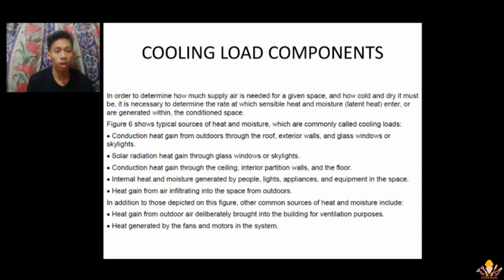Conduction heat gain from outdoors through the roof, exterior walls, and glass windows or skylights. Solar radiation heat gain through glass windows or skylights. Conduction heat gain through the ceiling. We have the internal heat and moisture generated by people. And we also have heat gain from air infiltrating into the space from outdoors. In addition to those depicted in this figure, other common sources of heat and moisture include heat gain from outdoor air and heat generated by the fans and motors in the system.